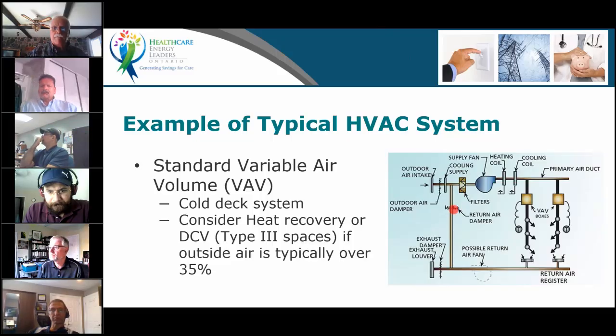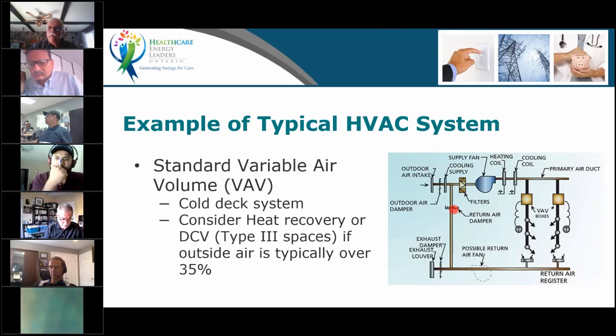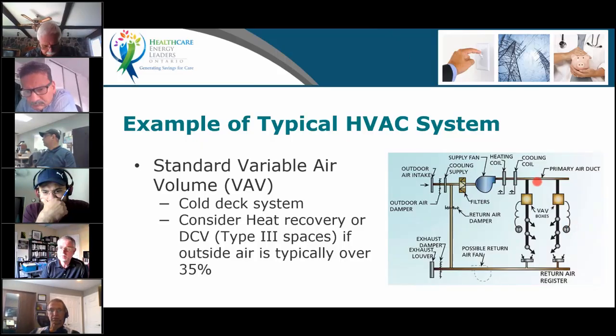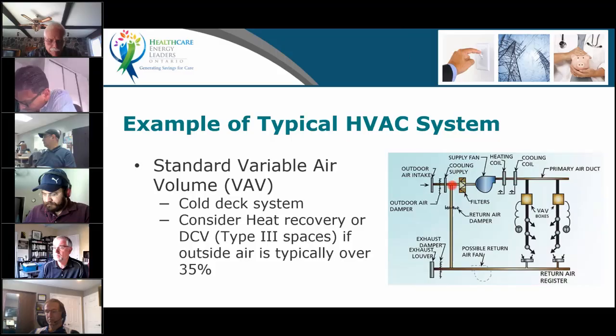When I told you some systems don't really deserve to have heat recovery, well, this system, in many instances, not all the time, does not require heat recovery because it's what we call a cold deck system. This fan will blow air that goes to VAV boxes that will modulate based on the space temperature, as a lot of you, I'm sure, already know. You will supply air between 13 and 18 degrees, typically. In an administrative area, you will have 85% return. I mean, it should be about 30% fresh air, but in practice we often see only 10 to 15%, so 85 to 90% return. That mixed air temperature is already warm enough that if you warm it any further, it will be too hot in the supply.